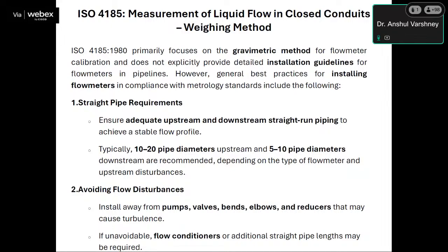However, best practice for installing flow meters in compliance with metrology standards includes the following points. A straight pipe requirement: it ensures adequate upstream and downstream straight run piping to achieve a stable flow profile. Typically 10 to 15 times pipe diameter upstream and 5 to 10 times pipe diameter downstream are recommended. In our lab at NPL, we are using more than 10 to 20D upstream length and more than 5 to 10D downstream length for calibration of these flow meters.